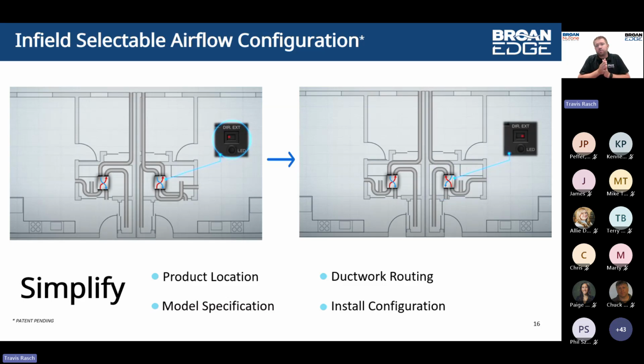Not sure if this is exactly where you're going, Craig, but if you have the desire to independently change the supply airflow rate and the exhaust airflow rate, meaning you intentionally unbalance the product, I have had applications where we're trying to produce a little bit of makeup air, or provide positive pressure on the envelope. You do have the ability to independently change the supply air and exhaust air CFM output in the minimum, medium, and maximum CFM settings. You can do that via the LCD screen and the related buttons, without any additional external controls.